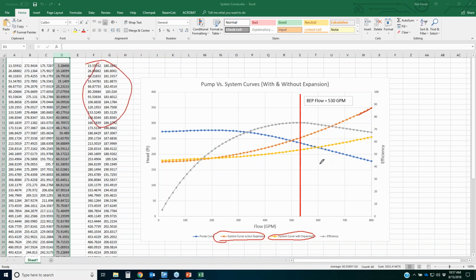So as you can see here, when I added on my expansion of the system, I don't have a unique system curve. It's not the same system curve anymore. So my system curve moves, okay? This red line right here, that's my best efficiency point. Well, my pump curve is going to keep operating on the same curve, however. So what happened in this situation is when I put on that expansion, my system curve moved. So I have a new system curve and my flow rate moved as well. So I'm operating at a higher flow at this location now.